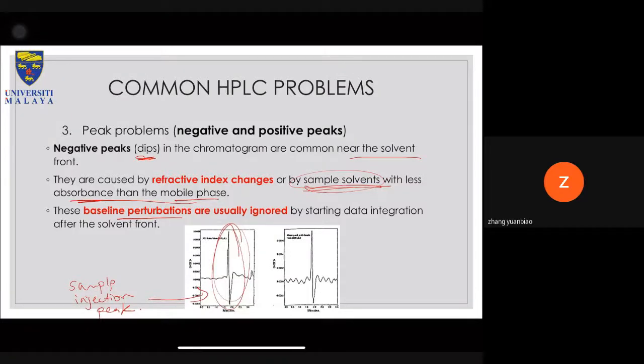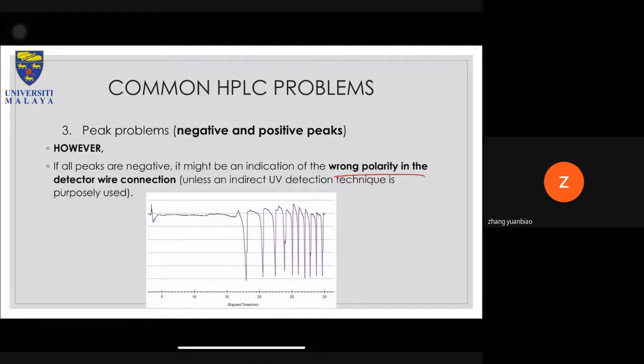However, if all peaks are negative, it might be an indicator of a wrong polarity of the detector wire connection. Okay, especially if you are using a PDA system, where it's a photodiode array. So a diode needs to have a certain polarity, plus and minus. If you switch it, it will still work, but it will give you the opposite reading, which is what happens here. Okay.